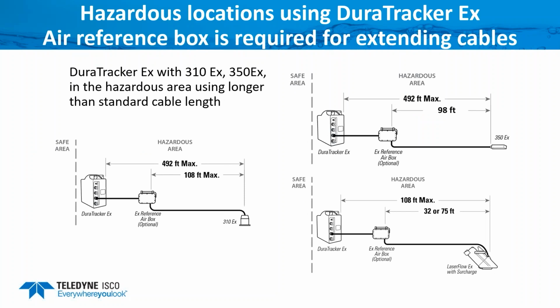The next thing I want to show you is the same scenario, but with an air reference box. What we're using this for is just to extend the cable length. Looking over here at the right, we'd still have our 98-foot cable, and we're going to reference atmospheric pressure right at the air box. We're also using that as a junction box, and now we can splice on more cable to go up to 900 or 492 feet. Same thing with the laser flow sensor: we have a maximum length of 108 feet, but it does allow you to extend your cable length if needed. And same with the ultrasonic sensor, with a maximum length of 492 feet.